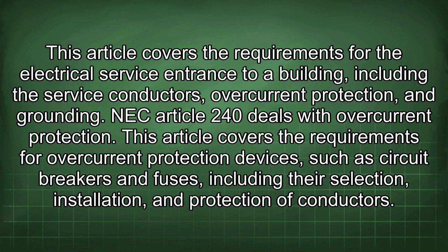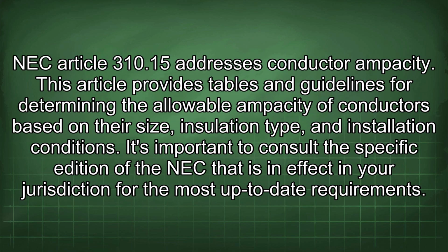NEC Article 240 deals with overcurrent protection. This article covers the requirements for overcurrent protection devices such as circuit breakers and fuses, including their selection, installation, and protection of conductors. NEC Article 310.15 addresses conductor ampacity. This article provides tables and guidelines for determining the allowable ampacity of conductors based on their size, insulation type, and installation conditions.